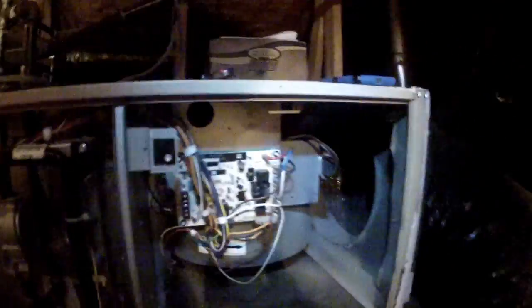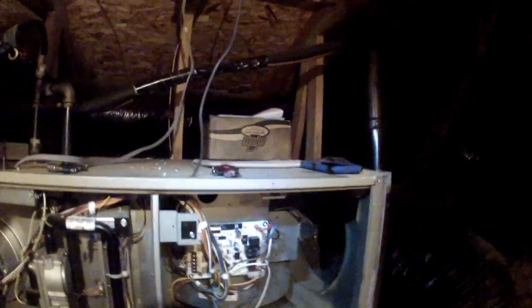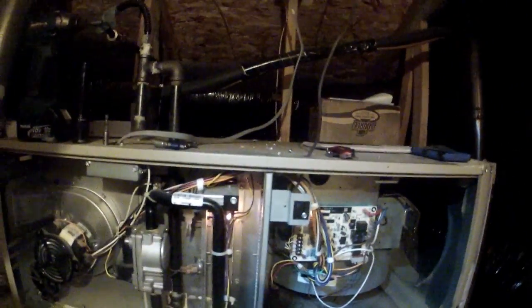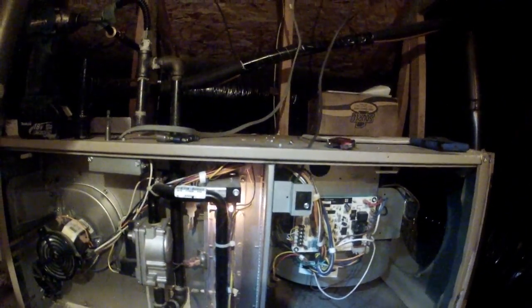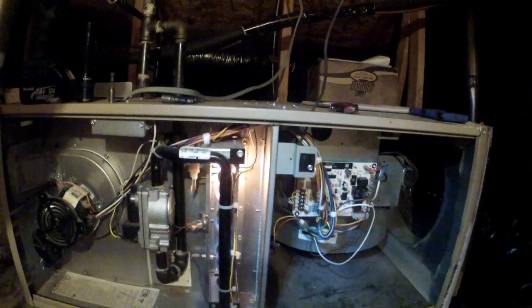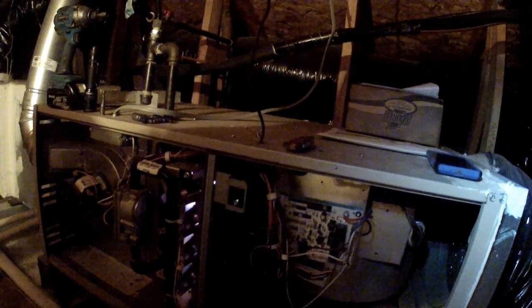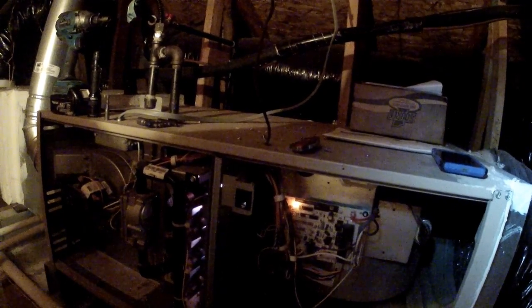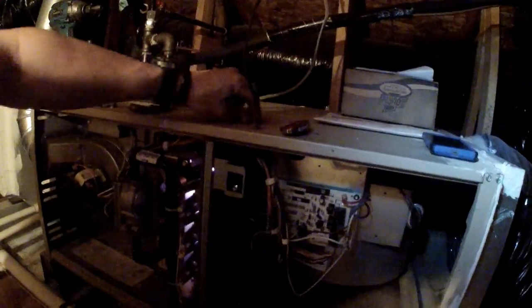24 volts, good 24 volts, good power. That's awesome. See if we get any crazy rapid amber lights going that time. Alright, hot surface igniter. Flame on. See if we get any crazy rapid amber lights or low flame sense. I think we'll be good to go now.